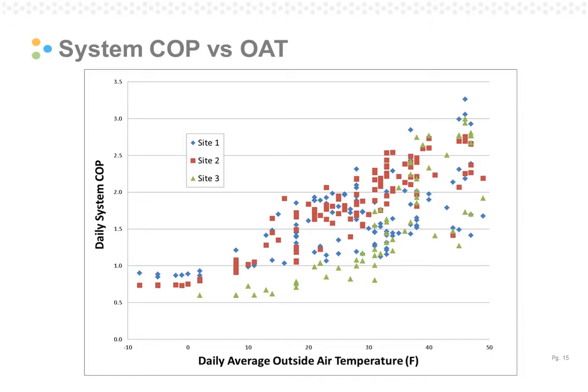So for the 3 sites, you can see that below 10 degrees Fahrenheit, the COPs start to level out. This is when the furnace is meeting the heat load of the home. But you can see that in the warmer temperatures, when the air source heat pump is meeting the heat load, in all 3 of the homes, the coefficient of performance is reaching up to 2.5 to 3.